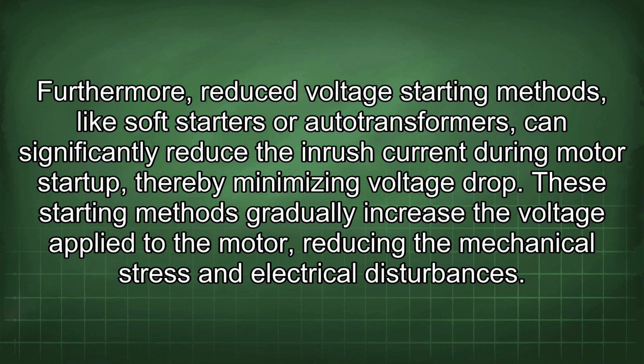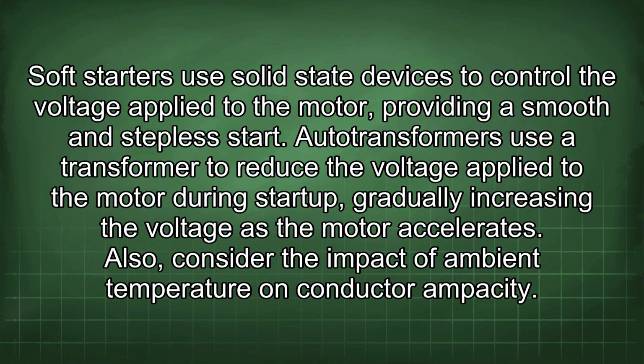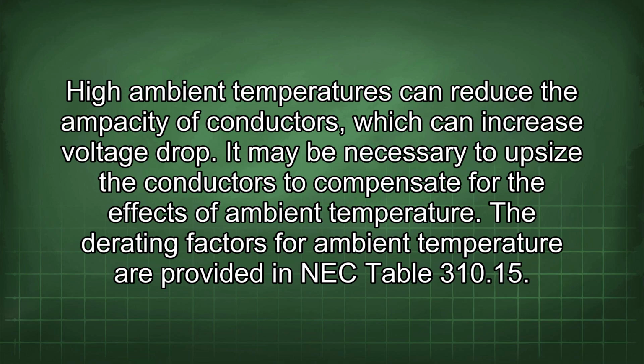electrical disturbances. Soft starters use solid-state devices to control the voltage applied to the motor, providing a smooth and stepless start. Auto transformers use a transformer to reduce the voltage applied to the motor during startup, gradually increasing the voltage as the motor accelerates. Also, consider the impact of ambient temperature on conductor ampacity. High ambient temperatures can reduce the ampacity of conductors, which can increase voltage drop. It may be necessary to upsize the conductors to compensate for the effects of ambient temperature.